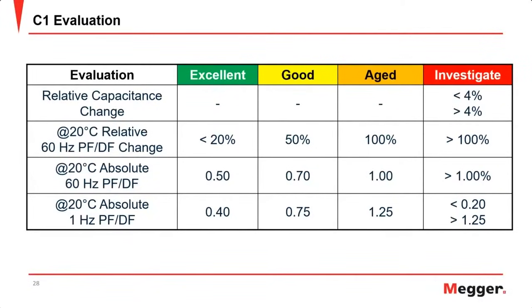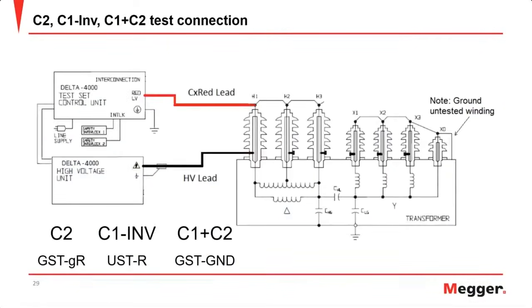Later in this presentation, I will talk about what this 1 hertz power factor dissipation factor is. After you've done the C1 test, your next test will be to perform C2, C1 inverted, and C1 plus C2. You'll see that this connection is very similar to the C1 test, with us swapping where the high voltage lead and the low voltage lead are connected.